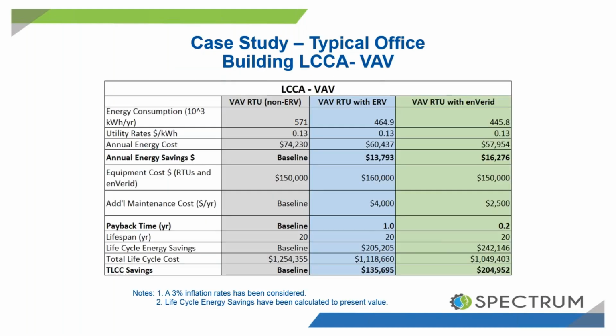From a costing perspective within a VAV system here, on a new construction project, the first cost was actually a little bit less, about break even with the original solution, $150,000. And then with the maintenance costs and whatnot, the total lifetime cost savings with enVerid was much higher. It was $200,000 versus $135,000 with ERV and conventional design. So phenomenal payback period on a new construction project, basically not costing anything.